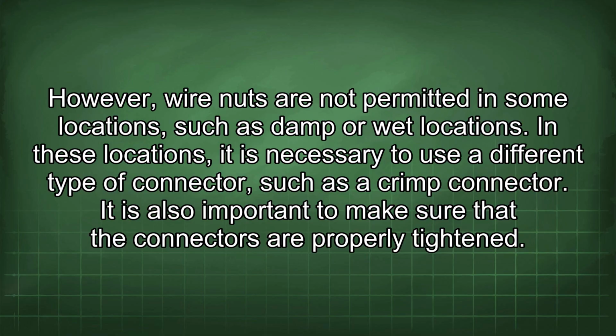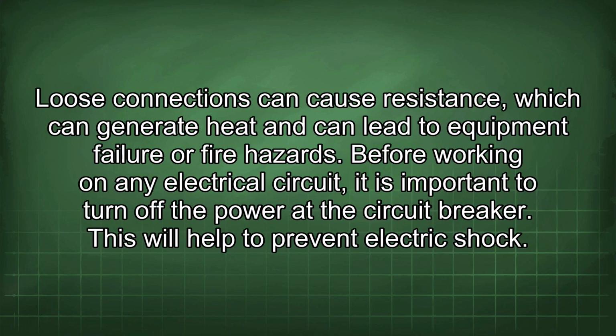It is also important to make sure that the connectors are properly tightened. Loose connections can cause resistance, which can generate heat and can lead to equipment failure or fire hazards. Before working on any electrical circuit, it is important to turn off the power at the circuit breaker. This will help to prevent electric shock.